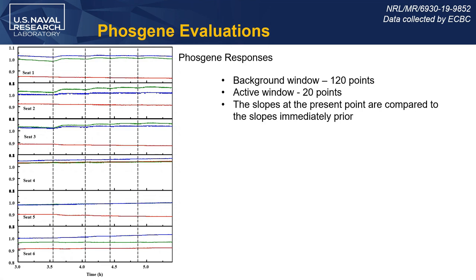This is where the algorithm can have issues. We really do need 120 points for a stable background condition; otherwise the background window changes almost as fast as the active window and the windows slide together. The 120-point window slides forward one point each time a new point is collected — that's how we correct for drift over time. Going down to a 15-minute background window makes it too short for stability and causes many false responses. To accommodate this, we quadrupled the entry of the first 15 minutes into the window — four copies each of the zero, 30-second, and one-minute time points.